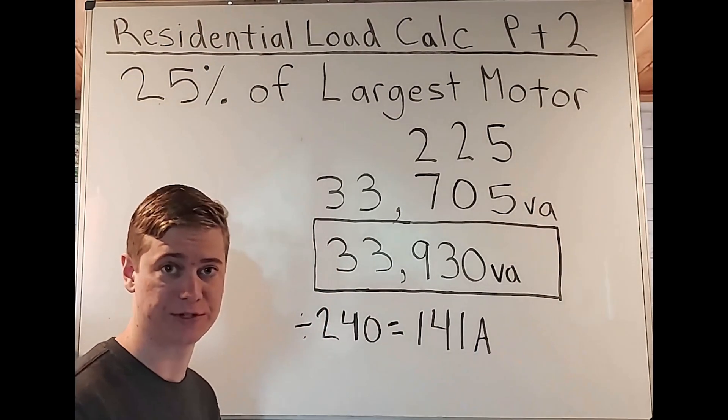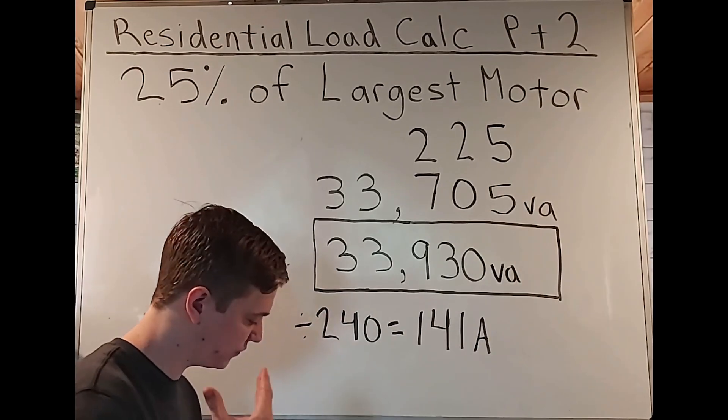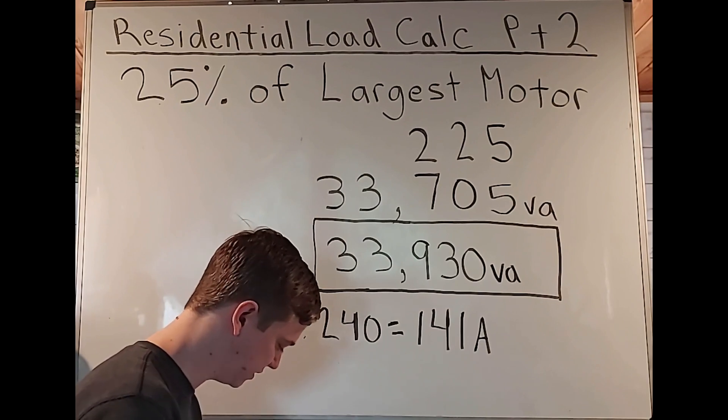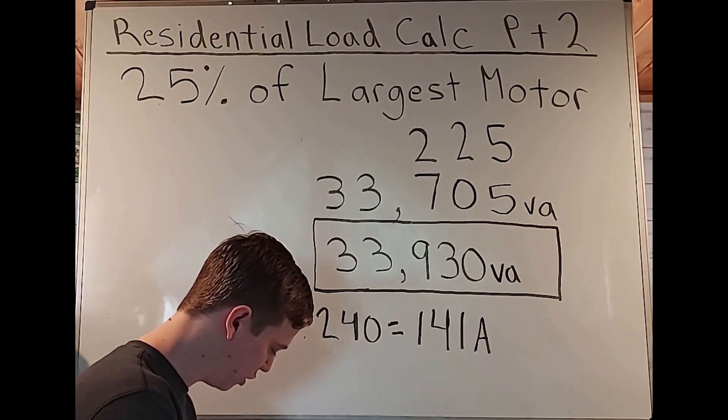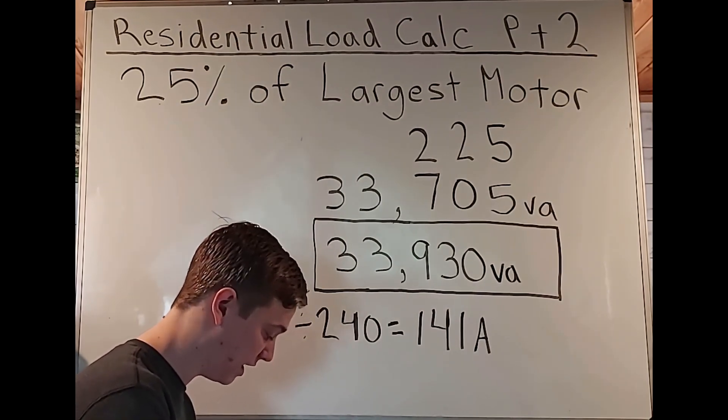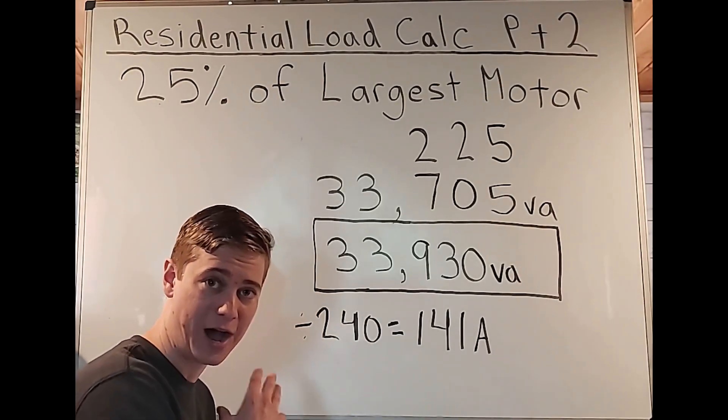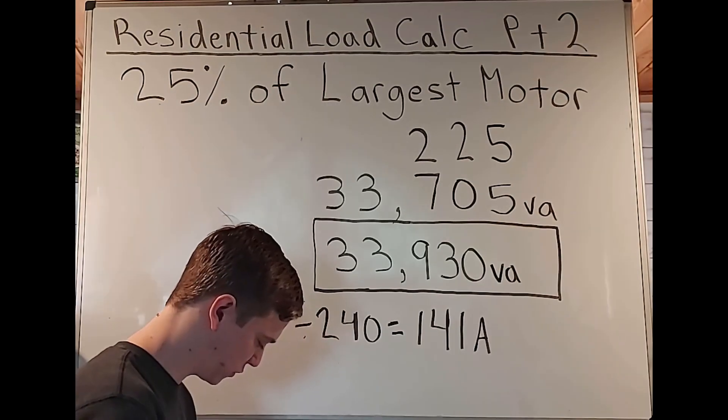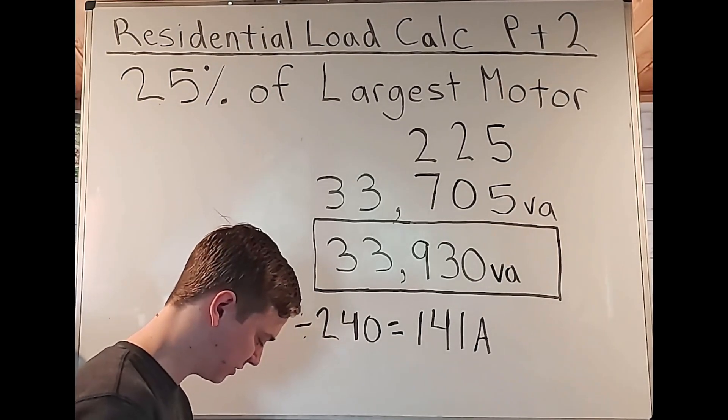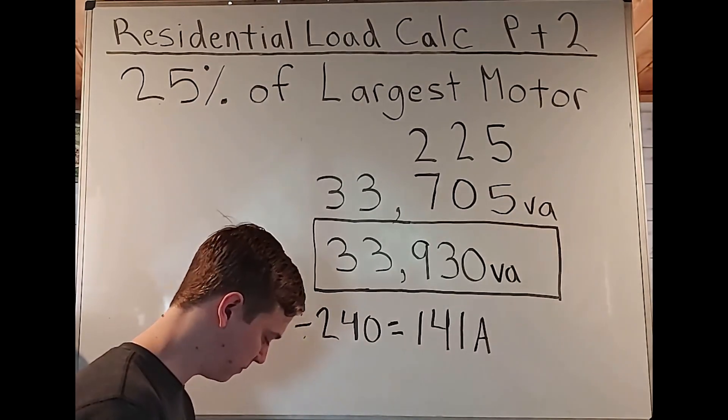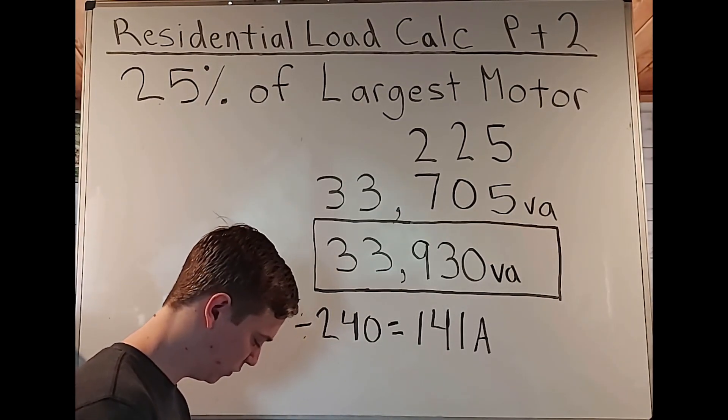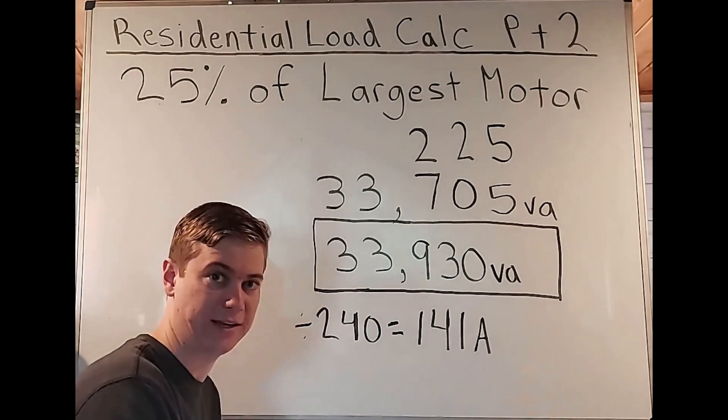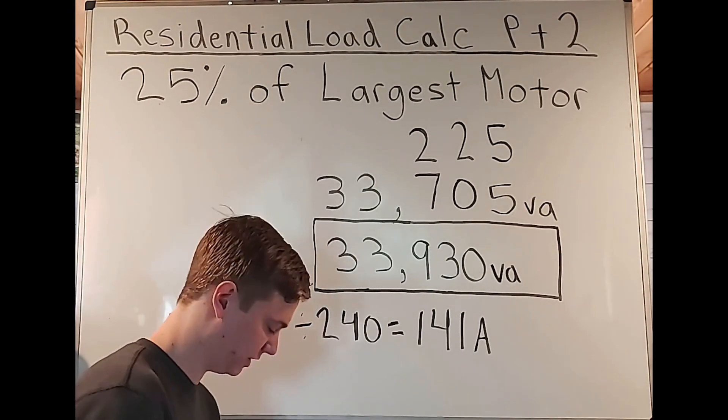Now that would be true, except for certain exceptions found in the code book. We're going to flip a page back and we're going to go to article 240.4 protection of conductors. We see under B overcurrent devices rated 800 amperes or less. So highlight this and remember this 800 amperes or less.